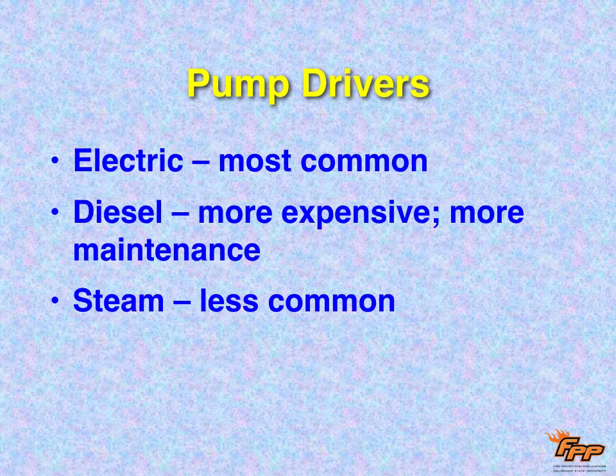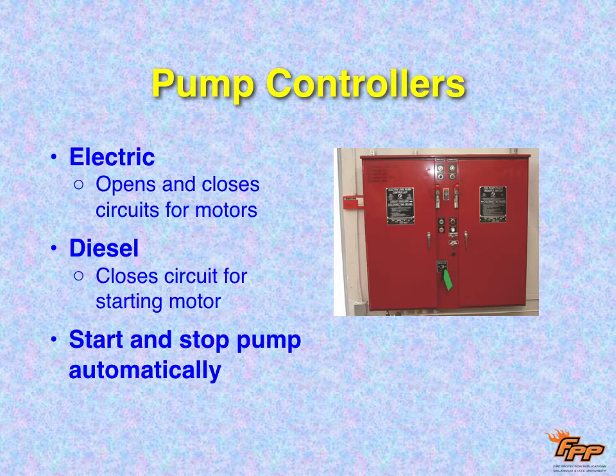And now, how are they going to be driven? Usually they're electric, but the electricity oftentimes goes out in fires, so they're going to be backed up by a diesel generator. Diesel's more expensive, has more maintenance, and is a little less reliable. Steam, maybe back east, you might see those in older buildings. The pump controllers are, again, going to be electric, and they start and stop the pumps automatically. But again, they're going to be backed up. Even if you have an electric system, that's going to be backed up by some kind of a generator.